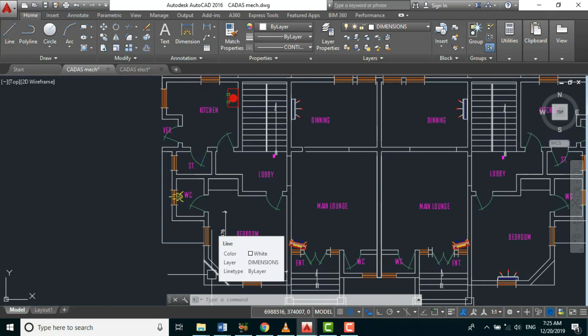The method I use in executing my design: for a space less than 13 square meters with moderate occupancy, we use a 1 horsepower single-phase AC. For a space less than 20 square meters with moderate occupancy, we use 1.5 horsepower. From 20 to 30 square meters, we use 2 horsepower.